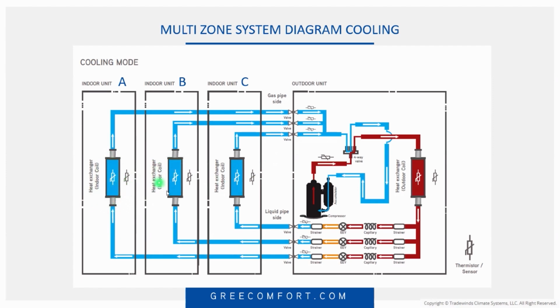So let's say I run this machine, but it's low on refrigerant, okay? Which is also going to do what? It's going to increase the discharge temperature. Because if I feed refrigerant to all of these indoor coils, and now I've got to get that cool refrigerant gas coming back to my compressor to keep it cool. Well, if I don't have enough refrigerant, what's happening here? I'm starving my return refrigerant gas coming back to that compressor. So if my gas coming back to the compressor is warmer, what happens to my discharge temperature? It gets hotter, right? Yep. No different than a restriction or anything else.